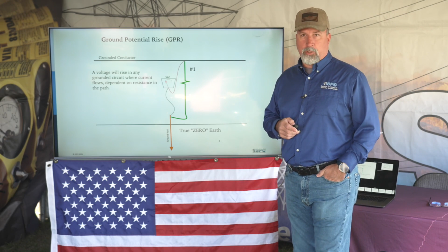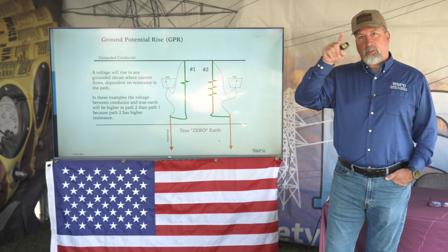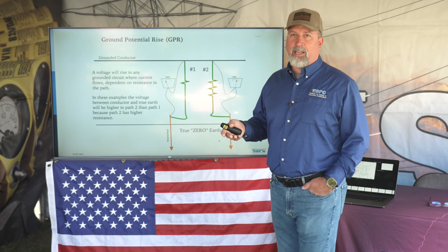As we install more grounds—the second, third, and so on—we create a path in our grounded conductors for current to flow. So if you have induction, a fault, or any form of induced voltage, current is going to flow in that circuit. That's okay as long as you understand that and don't become part of that circuit or break it and become the new path for voltage and current to flow. The resistance in those temporary grounds is proportional to the voltage you're going to see in that pathway.